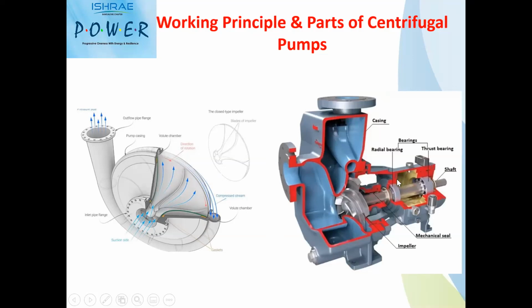So the main parts of the pumps, as I explained, in a typical cut section of an end suction pump, you will have the impeller, the casing, the bearings and the shaft. Here the prime mover, that is the motor or engine, is connected. So water enters from here. Since the impeller is rotating, it creates a centrifugal action which will guide the water through the volute of the casing and exits from the discharge side of the pump.